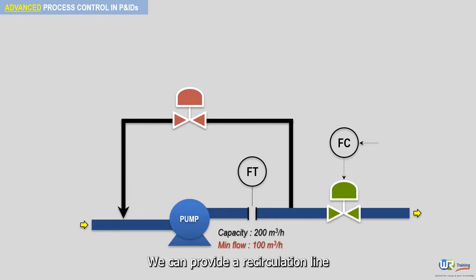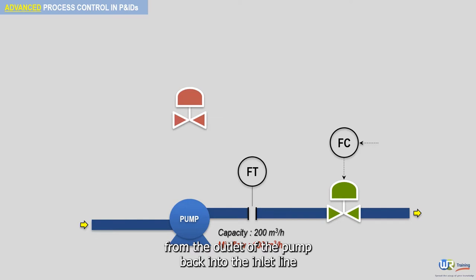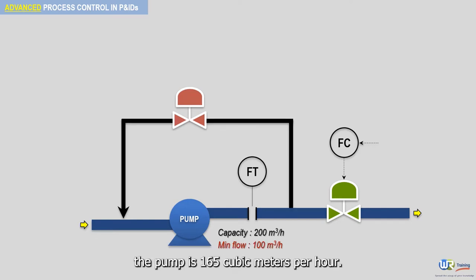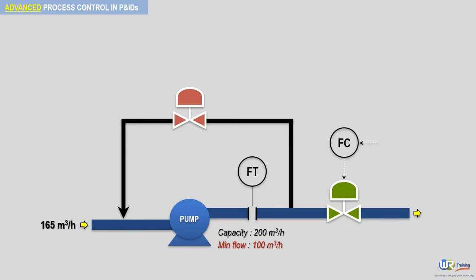We can provide a recirculation line from the outlet of the pump back into the inlet line. If the flow rate into the pump is 165 cubic meters per hour, the pump is happy since its actual flow is higher than the minimum flow.